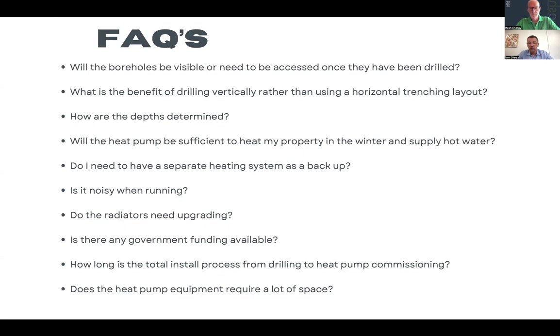Do I need to have a separate heating system as a backup? On smaller domestic properties, the majority of the heat pumps that we use have built-in immersion heaters. We also install immersions in the hot water cylinder as a double backup for the hot water. For larger commercial properties, that is really down to the client. We work with good manufacturers, so we've got good backup. We don't recommend doing this, but it's entirely the client's choice.